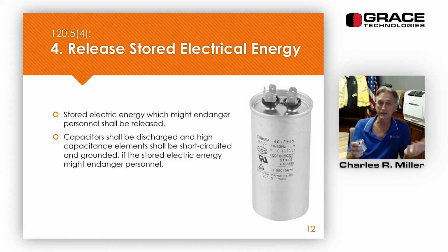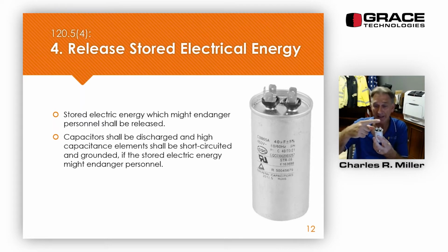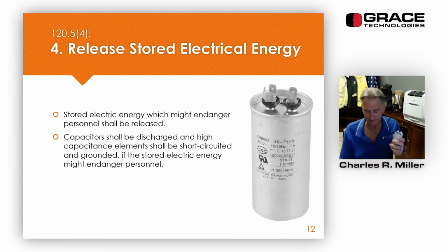Release stored electrical energy. Stored electrical energy that might endanger personnel has to be released. Capacitors have to be discharged, and high capacitance elements shall be short circuited and grounded if the stored electric energy might endanger personnel. I've got just an air conditioner compressor capacitor, and typically for small loads like this, small capacitors, you'll just take a screwdriver and touch the contact points to discharge it.